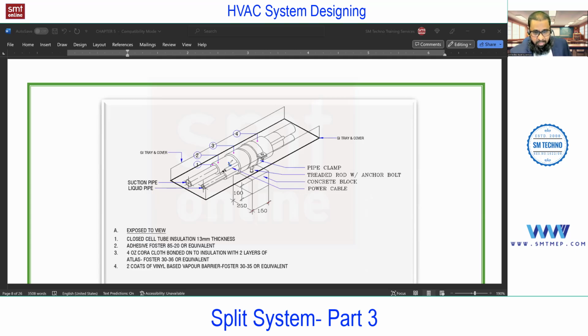So all this complete is going to run, as per standard, with the 3-inch PVC conduit. And if it is running on the roof or above the false ceiling, this should be with a separate drain tray. You see the GI tray as per standard. Generally, we are not using all this in detail, but as per standard, this is required. For a standard project, you must follow all this detail drawing, because they will do the inspection.